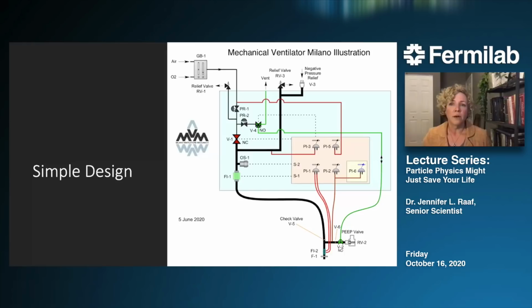Here's the design. The components that make up the MVM are inside the light blue box that you see. And as I said before, it just needs an electrical outlet and a source of pressurized medical air and oxygen. That's available in most emergency rooms and intensive care units. But in the absence of a wall hookup for pressurized air, you can use a portable tank. Starting at the top left of the image, you can see where the air and oxygen enter a gray box that's labeled GB1. That is an off-the-shelf gas blender to allow you to adjust the fraction of oxygen that the patient breathes. Normal air that you breathe is only 21% oxygen, but sometimes it's useful to have patients with respiratory problems breathe air that has a higher percentage of oxygen.